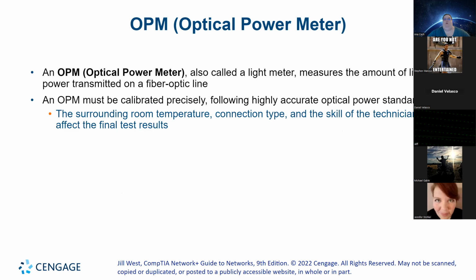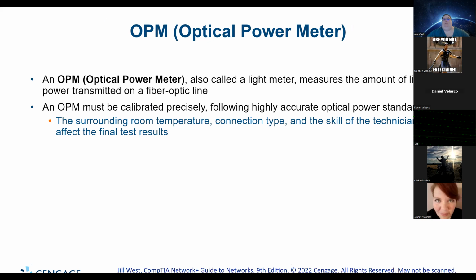OPM, or optical power meter, also called a light meter, measures the amount of light power transmitted on a fiber optic line. An OPM must be calibrated precisely, following highly accurate optical power standards. The surrounding room temperature, connection type, and the skill of the technician all affect the final test results.